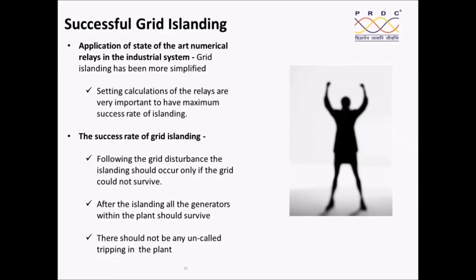Therefore, successful grid islanding means application of numerical relays, so the setting calculations of the relays are very important, and we have to ensure that for each and every relay setting, the various simulation studies are conducted. Then we will be able to ensure that proper islanding is there. When we say that my islanding is successful following the grid disturbance, islanding should occur only if the grid could not survive.